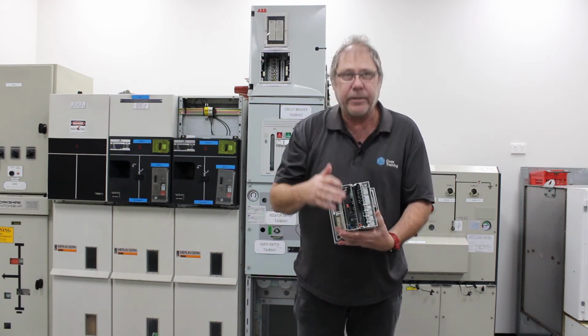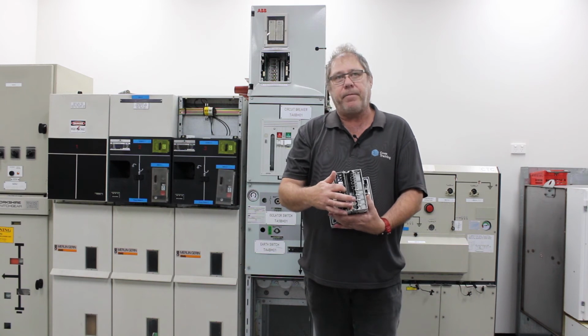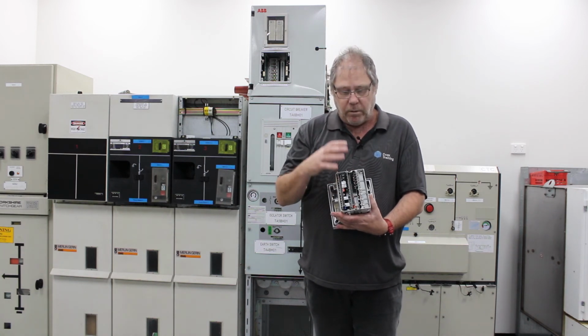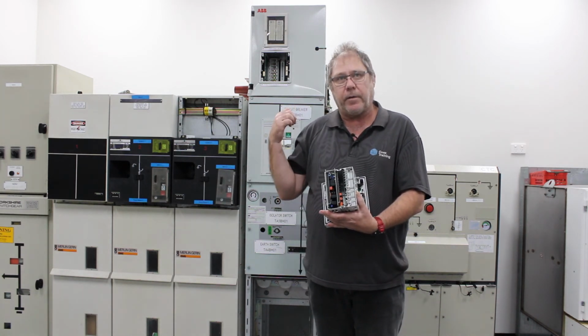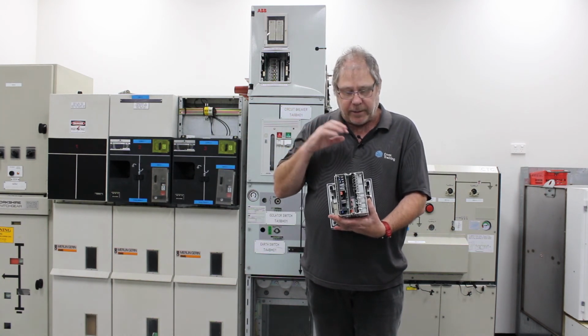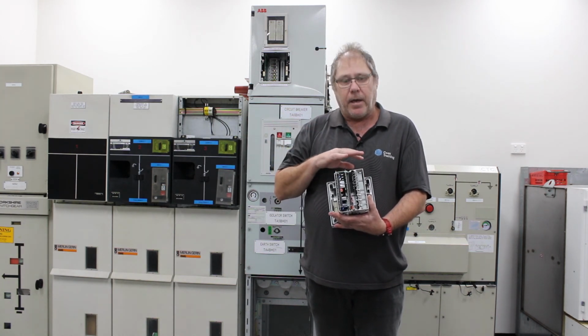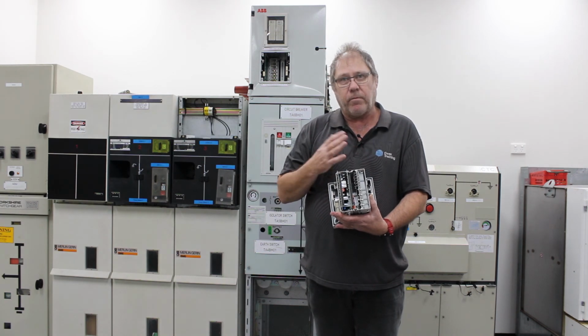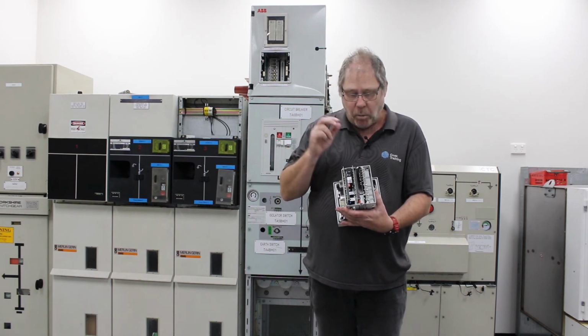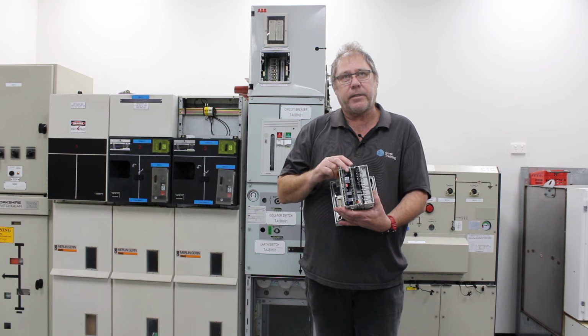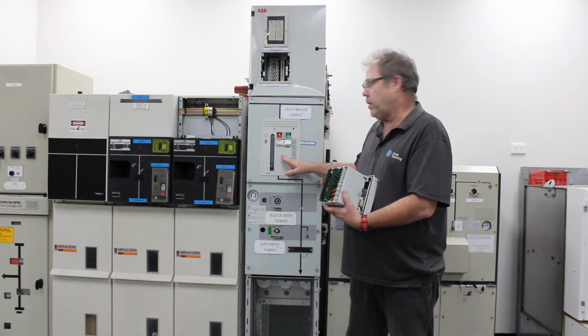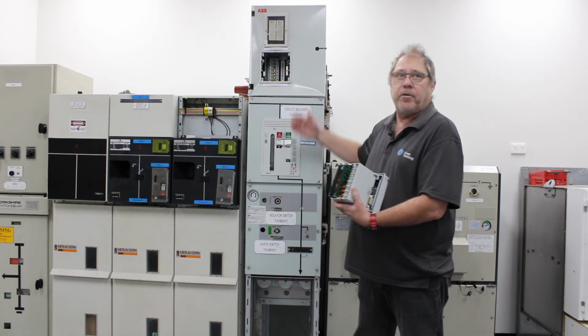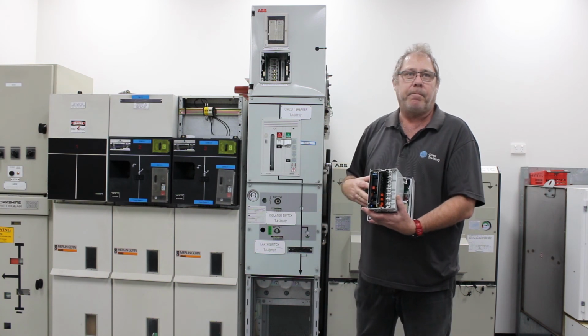All the small relays inside here are the relays that control the tripping regime for this particular circuit breaker. So when the CPU in here gets an out of specification reading, such as an overcurrent, one of these relays will react by sending a signal to the trip coil of the circuit breaker and trip it out just like that to clear the fault.